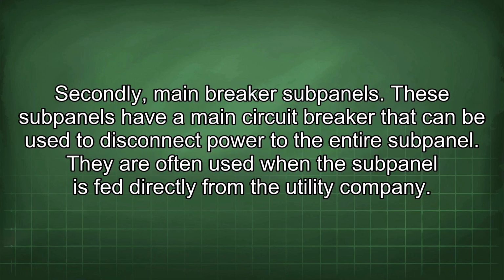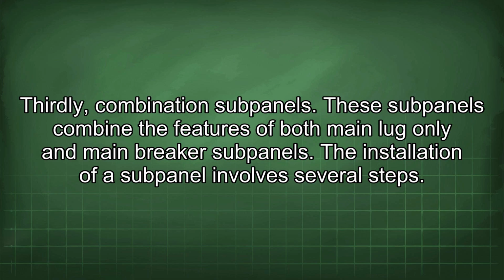Secondly, main breaker subpanels. These subpanels have a main circuit breaker that can be used to disconnect power to the entire subpanel. They are often used when the subpanel is fed directly from the utility company. Thirdly, combination subpanels. These subpanels combine the features of both main lug-only and main breaker subpanels. The installation of a subpanel involves several steps.